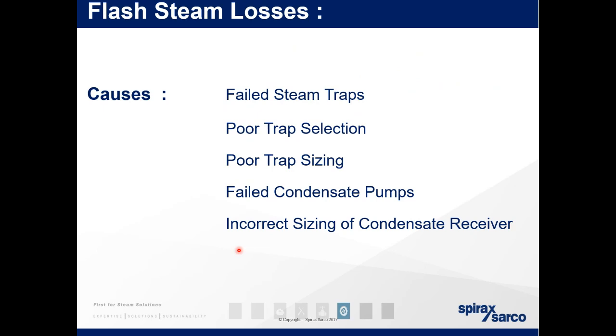So, causes. Failed steam traps. If you have a steam trap which is passing steam rather than condensate, that's going to make its way down your line, probably to your feed tank, and you'll see steam venting from the top of your feed tank. Poor trap selection. By choosing the wrong type of steam trap, you can cause losses. And poor trap sizing. An undersized trap or an oversized trap is going to cause inefficiencies in your system. As a general rule of thumb, when selecting the size of trap you need, you take the load that your process is using, say it's 500 kilograms, and you double it. So you size a trap for 1,000 kilograms in this case.